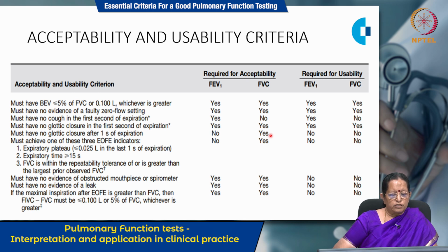Then end of forced expiratory indicators. Whenever there is an end of forced expiration, I told you that the expiratory plateau should be less than 0.025 liters in the last 1 second of expiration. So for FEV1, because FEV1 is calculated in the first second, that is not required for accepting FEV1, but for FVC measurement that is needed. But for usability this is not needed.